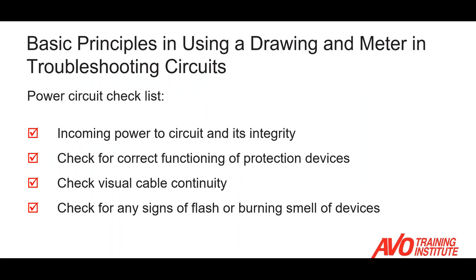Checking the power circuit, we can use a checklist. We need to check the incoming power supply and its integrity, check the functioning of our protection devices, do a visual check on cable continuity, and look for any signs of flash or burning. We need to use our senses — sight, smell, touch — to see if we can detect anything.